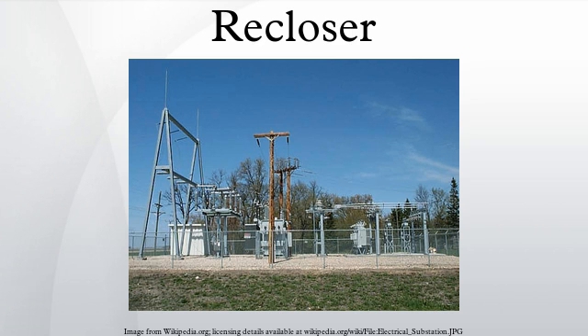Reclosers in action: residential customers in areas fed by affected overhead power lines can occasionally see the effects of a recloser in action. If the fault affects the customer's own distribution circuit, they may see one or several brief, complete outages followed by either normal operation or a complete outage of service. If the fault is on an adjacent circuit, the customer may see several brief dips in voltage as the heavy fault current flows into the adjacent circuit and is interrupted one or more times. A typical manifestation would be the dip, or intermittent blackout, of domestic lighting during an electrical storm.